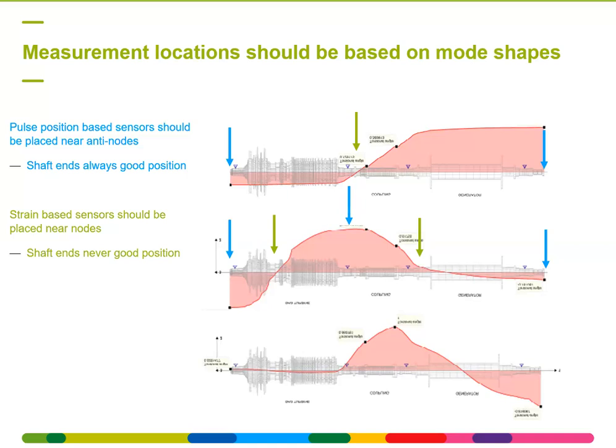You can see from the deformation that along the gas turbine and the compressor, there's almost no relative twist. So there's no torsional shear strain there, neither in the generator. The only deformation, the twist, all happens in the intermediate shaft in between the gas turbine and the generator. So that's where you would position your stress-based sensor. The pulse-based would be less ideal to be placed there.